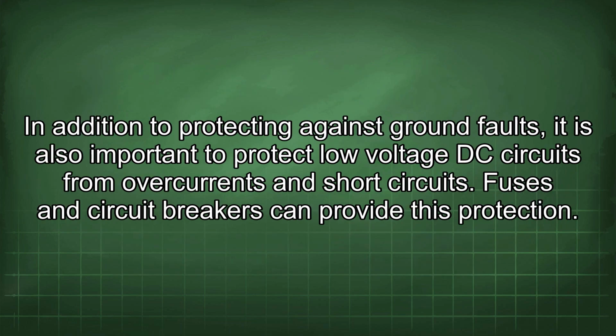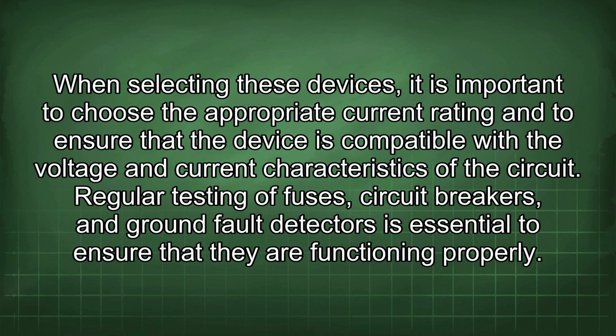In addition to protecting against ground faults, it is also important to protect low-voltage DC circuits from overcurrents and short circuits. Fuses and circuit breakers can provide this protection. When selecting these devices, it is important to choose the appropriate current rating and to ensure that the device is compatible with the voltage and current characteristics of the circuit. Regular testing of fuses, circuit breakers, and ground fault detectors is essential to ensure that they are functioning properly.